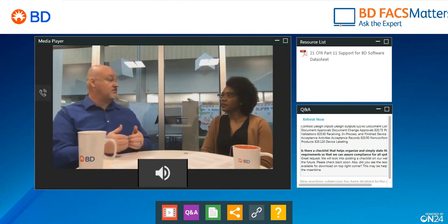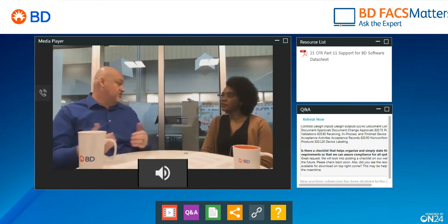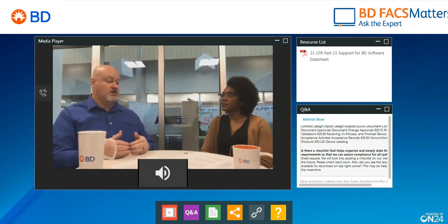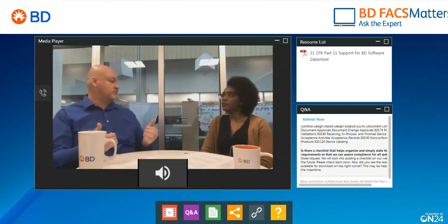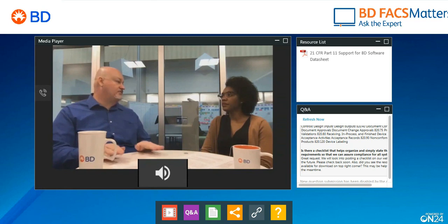Those records are required to be provided to the FDA if they come on site for an inspection. Or maybe if there's a specific reason, they'll request it and you send it to them. So if you have a system doing that, Part 11 is compliant there. If we have a system where there's no predicate rule, nothing that the FDA would want, then there's no requirement for Part 11 to apply.